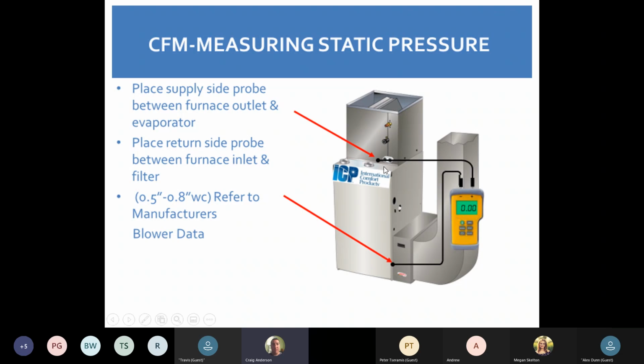So if you don't have a manometer that's reading static pressure or the static pressure tips, get out there and get one. If you haven't done static pressure, go on YouTube. They have a lot of videos, about 5 minutes, 7 minutes long. Fantastic. They're going to teach you how to do your static pressure between your return and your supply. There's also a lot of coils out there that have a lot of big static resistance on them. So it'll show you how you can test your filter static or your coil static to see how much resistance we're getting through that at that time. Big thing to be doing out there. Make sure you're doing your static pressure and your temperature rise.